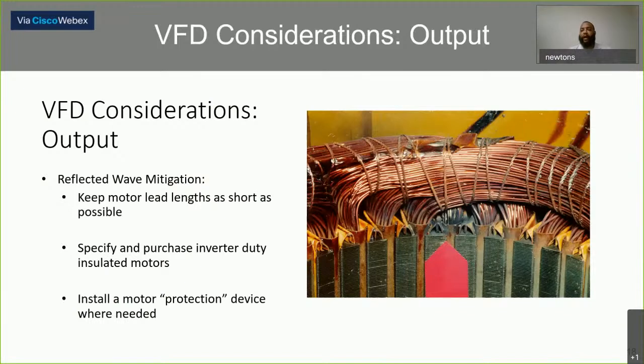Reflective wave is basically a phenomenon that happens when you have a very long cable length, and it causes the voltage to spike, a lot of times sometimes double, at the point where there's an impedance mismatch. In this case, a lot of times it's going to happen at the end of the cable and your motor termination box. There are other names for that, but for this presentation, we're going to call it a motor termination box. And you can see in this picture some of the effects. This picture shows a winding inside of a motor that's been affected heavily due to reflective wave. Well, how is this so?